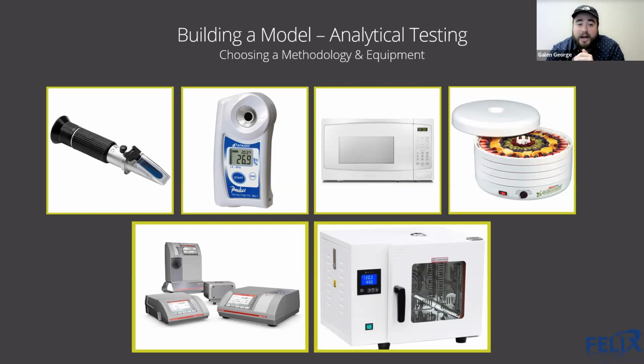Now, as you can imagine, optical refractometers require a lot of expertise and experience to use, and can easily be biased from one operator to another. You can eliminate that by moving to something like a digital pocket refractometer that you can use out in the field. However, these can also be prone to errors. They aren't as finely tuned. They're more robust for field work, but they might not have temperature correction in them. So temperature has a huge impact on the refractive index of liquids.